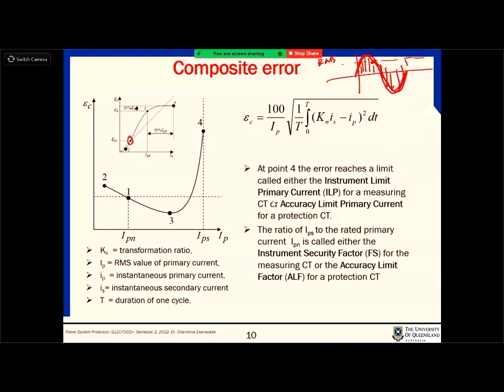So that limit is called, for instrument, limit primary current. For measuring CTs, there are 2 different names. When you are going with the measuring CTs, that limit is given a different name. If you are using a protective CT, that limit has been given a different name. So for a measuring CT, it's called instrument limit primary current. So you are not going beyond that. I don't want to do any measurements, right? That is the instrument limit. But when you are going to the protective CTs, you call it accuracy limit primary current, right? So that beyond that, the accuracy drops, right?